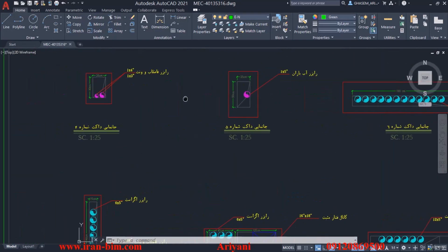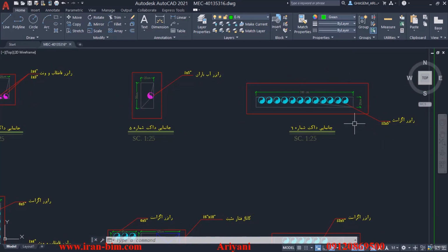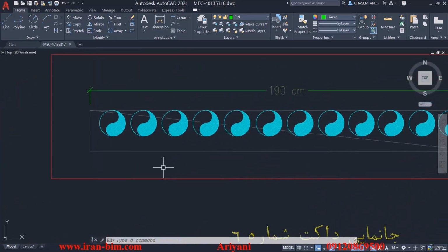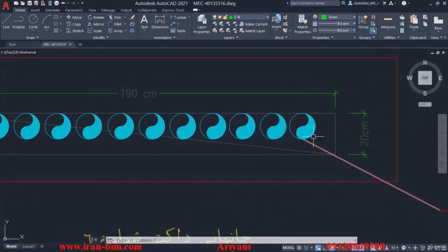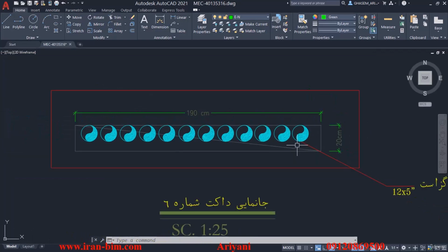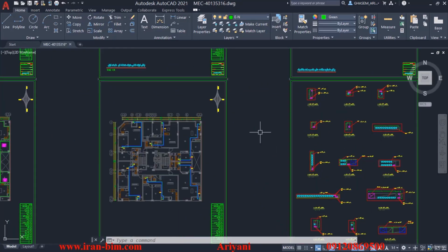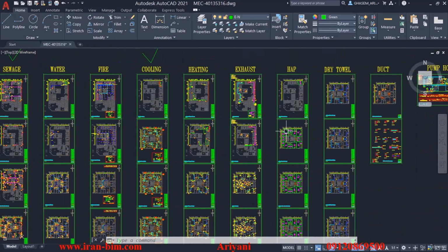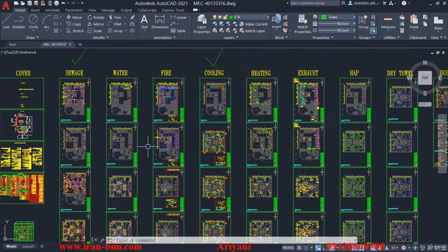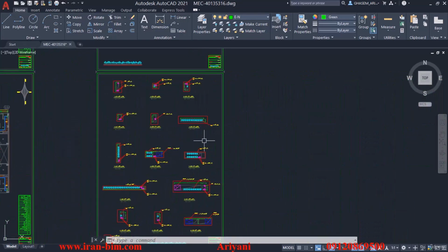So as I've previously stated, we can't really trust the specifications of these sections because, for example, here it says 1.9 meters, but they haven't actually taken the hangers into account, and there are a lot of issues that might happen that are not visible in the 2D view, like when we had the plumbing fixtures on top of the beams, and events like these which they haven't actually thought about, which will cause some changes in the paths, which will cause uncoordinations.